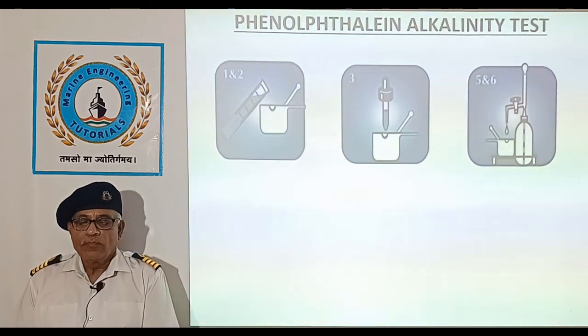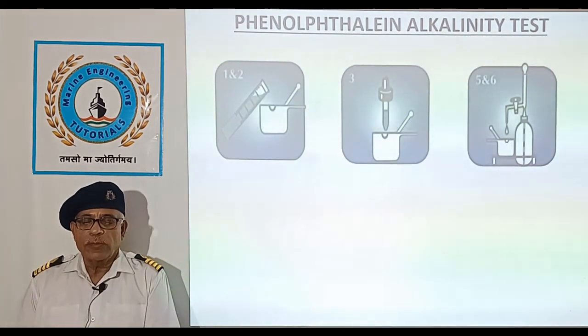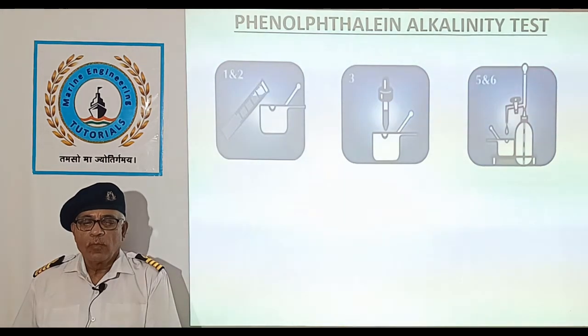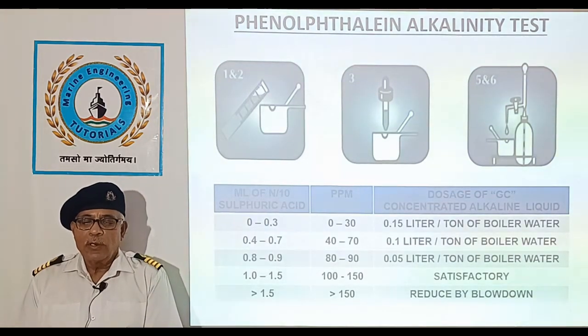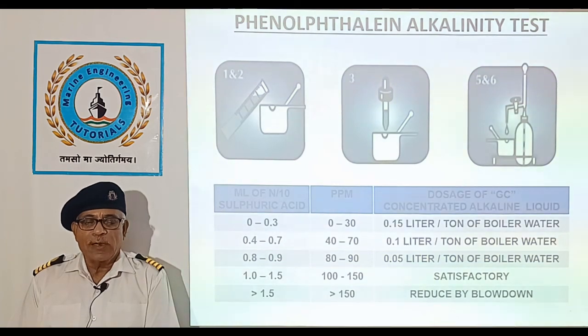Add sulfuric acid drop by drop until the pink color disappears. Note the level of acid in the burette, convert millilitres of sulfuric acid used as per the table, and record the result in ppm as P-alkalinity. Adjust dosage as necessary.